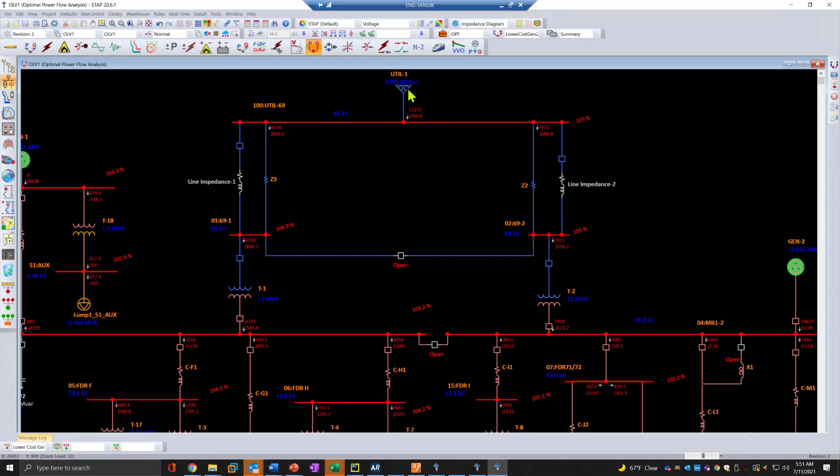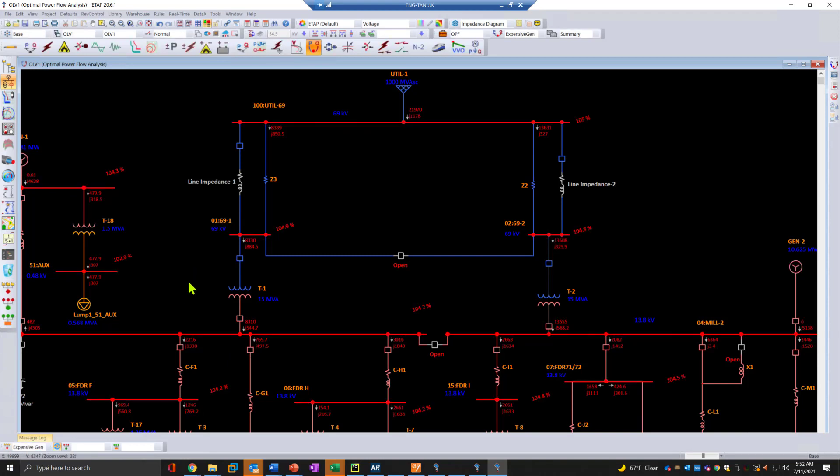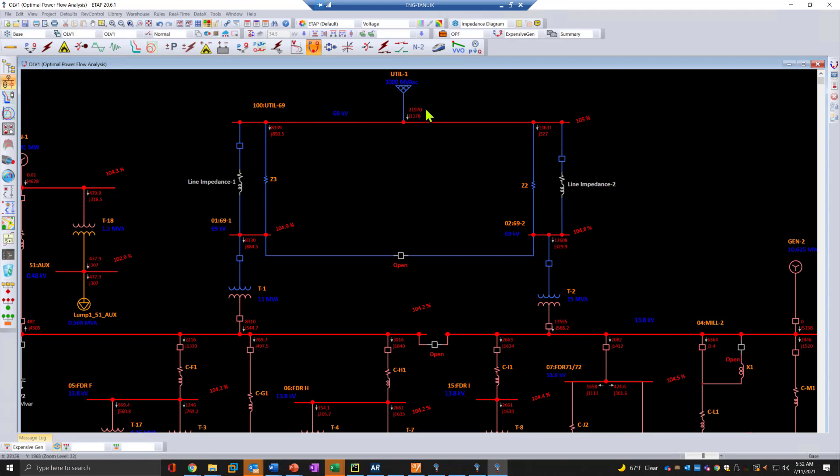Finally, when we have our generator which is expensive, both generators are expensive. In both cases the real power essentially goes to 0 megawatt and we are using them again purely for the reactive power. Maximum power, almost 22 megawatts, is now actually coming from the grid. This could be a case where we have switched the fuel on the generator and the cheapest source based on the energy price and the loading of the system happens to be the grid.